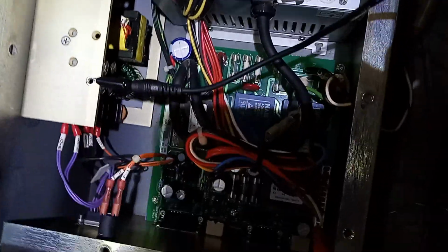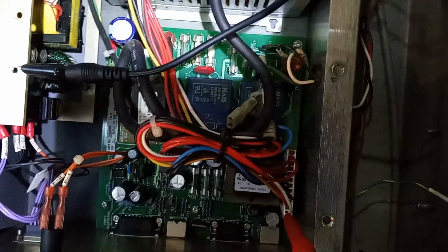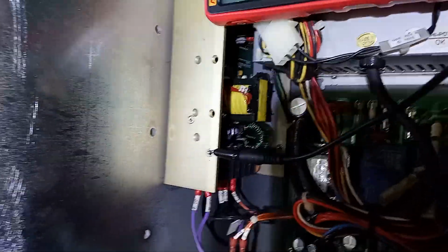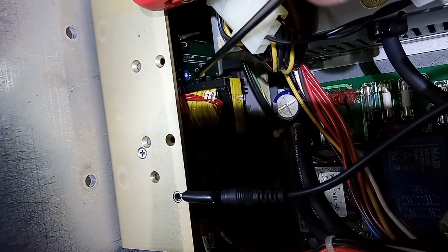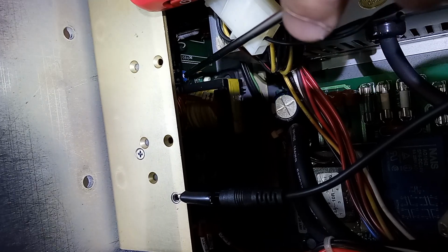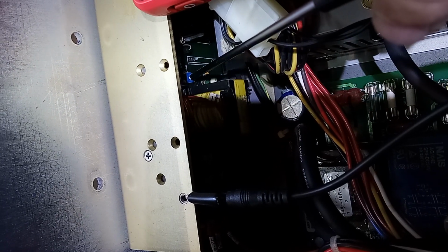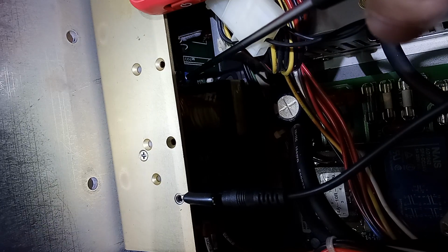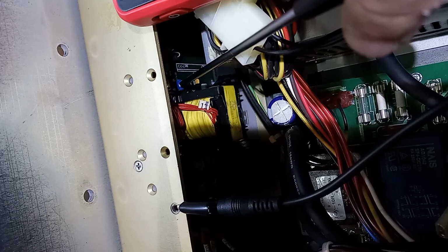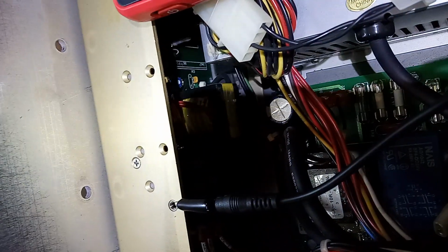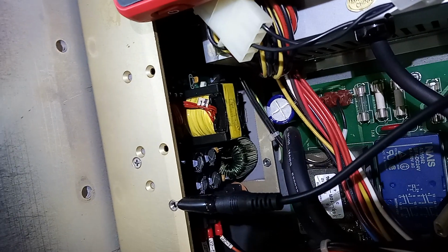The next thing we're going to measure is all these fuses. We'll power off the machine and do a continuity test on all those fuses right there. Now, if any of those voltages are off, there's an adjustment screw right here - a bit difficult to see with the camera, but it's right here. It's a blue and white potentiometer, where you'll get your screwdriver in. See the blue and white potentiometer? That's where you'll do the adjustment if anything's off. Mainly the 24 volt and the 5 volt line would normally be adjusted from there.